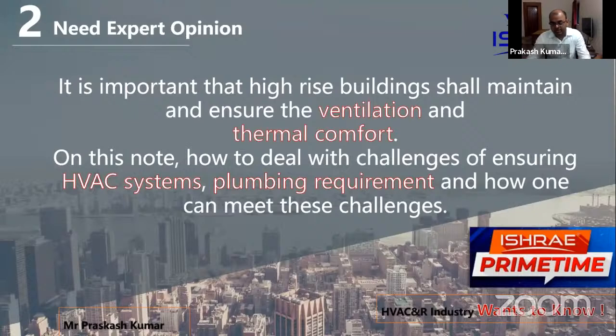Now a recent development which we are doing, actually I would not say it is recent, but for the last 10 years, is that we are using the supply air duct, in case of emergency, as a fume suction duct as well. So what we do is we provide a motorized damper just after the AHU, and from there a duct is laid to the roof, and there is a fan installed which sucks the air in case of fire.